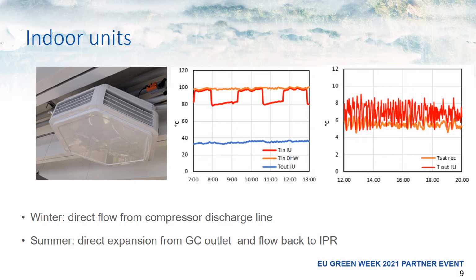This is an example of indoor unit of the Trento supermarket. So it's a coil which is hanging from the ceiling and which is directly fed by the hot CO2 from the compressor discharge line during the winter time, and by the expansion of CO2 after the gas cooler during the summer season. So in the winter season, we have hot CO2 entering here the coils at a temperature which is between 80 and 100 degrees, and it's flowing back to the unit at 35 degrees. That depends on the ambient temperature, internal ambient temperature.